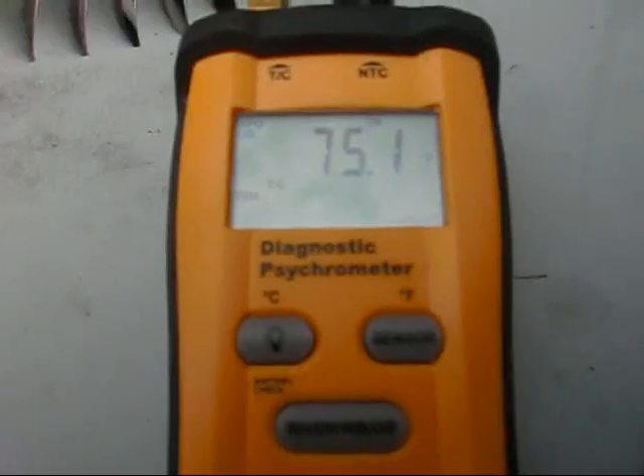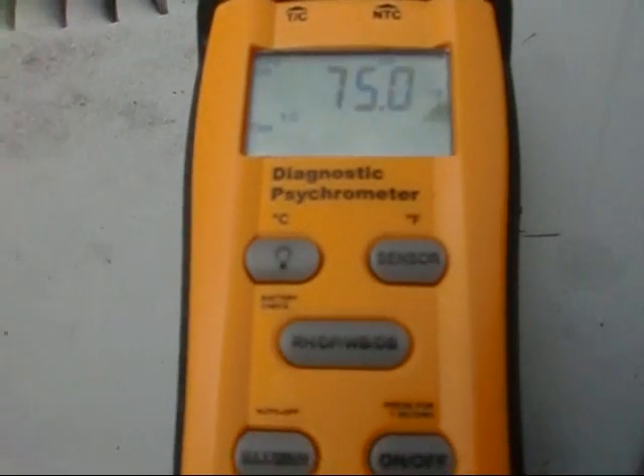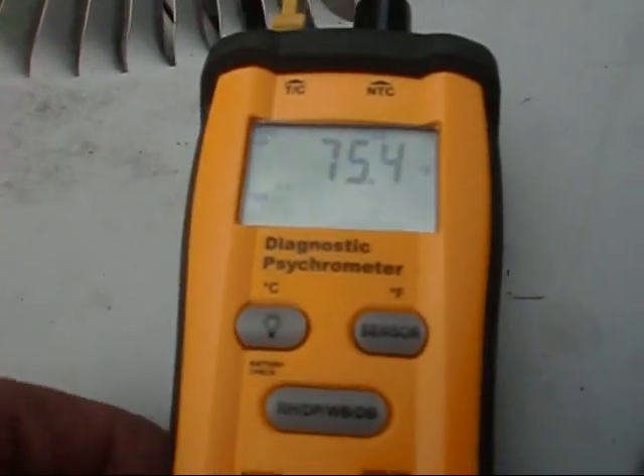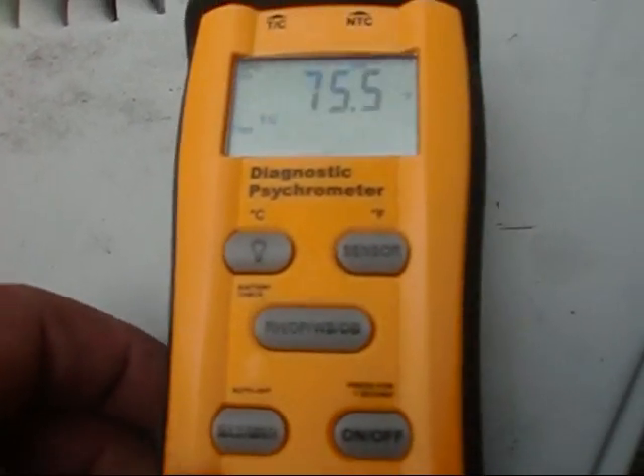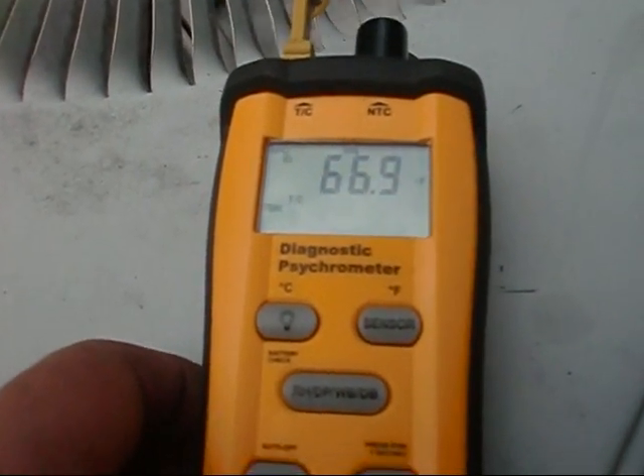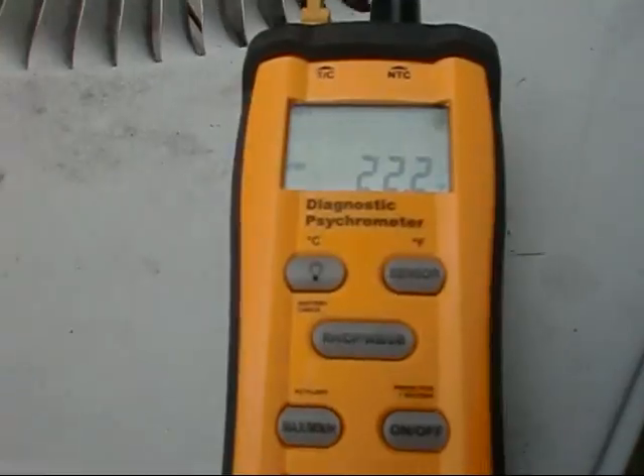We've got our wet bulb probe in here and we're getting 66.9. We remove the thermocouple and then get our outdoor dry bulb — 75 degrees. We press enter, hit output, and that's going to give us a target superheat of 22.2 degrees.